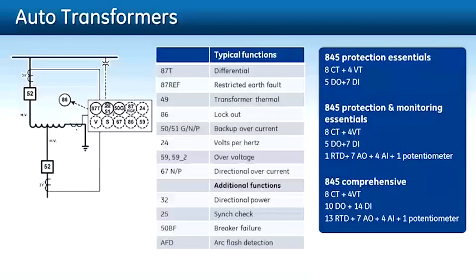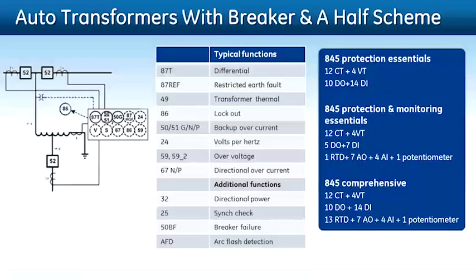Auto transformers is another common application that you see more in the transmission space. This can also be met similar to a two-winding transformer application. The core functionalities remain the same between the two. You can build differential, restricted ground fault, and voltage-based overfluxing and so on functionalities for auto transformers, and 845 can easily meet this need also. The next application is auto transformers with breaker and a half scheme. This is in the same way we talked about a two-winding transformer with breaker and a half scheme. You will pick a three-winding application ordering option in 845 in order to deploy it for an auto transformer with breaker and a half scheme. The rest of the monitoring and diagnostic functionalities remain common across any of the application scenarios you are picking.